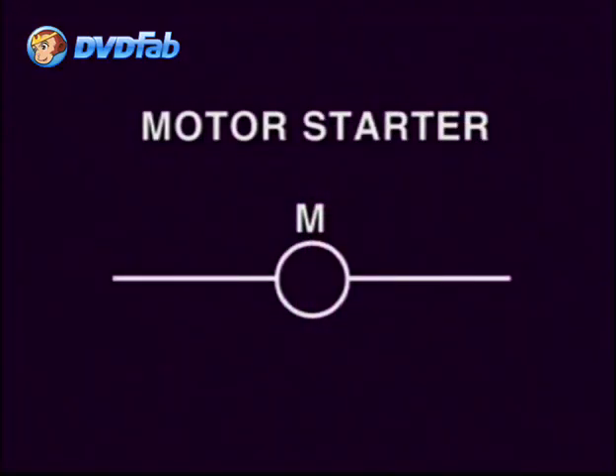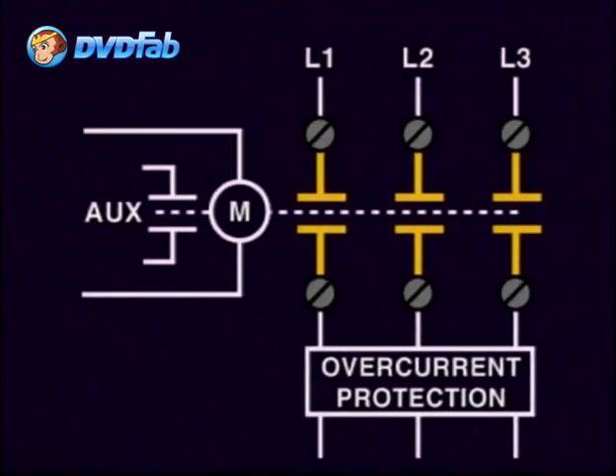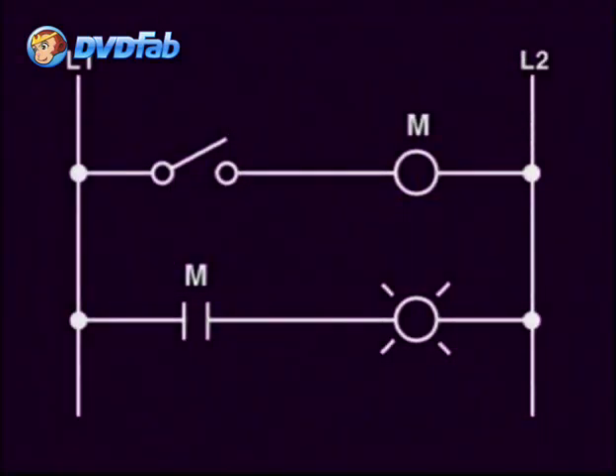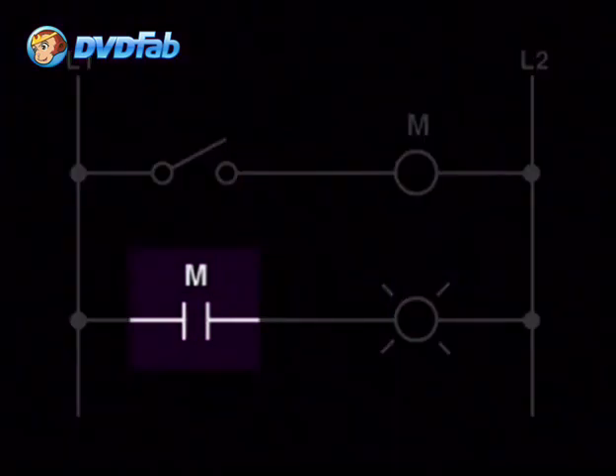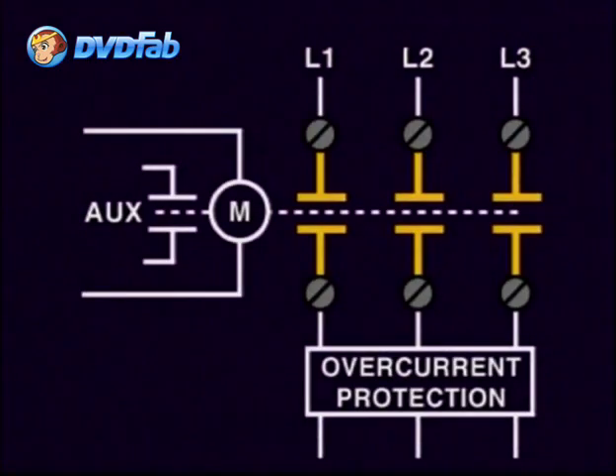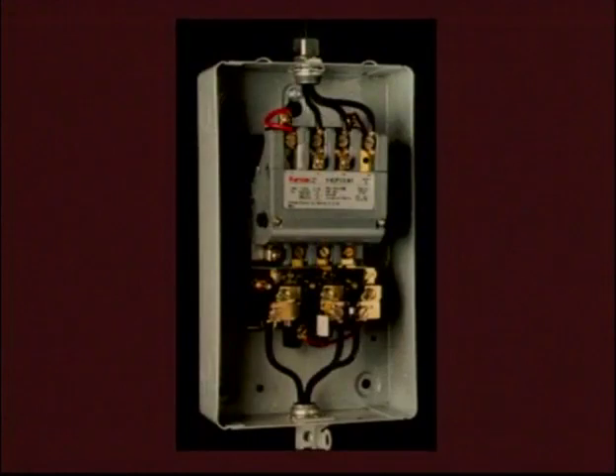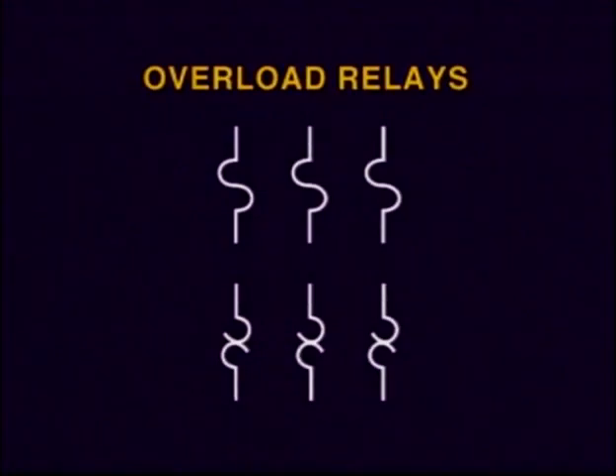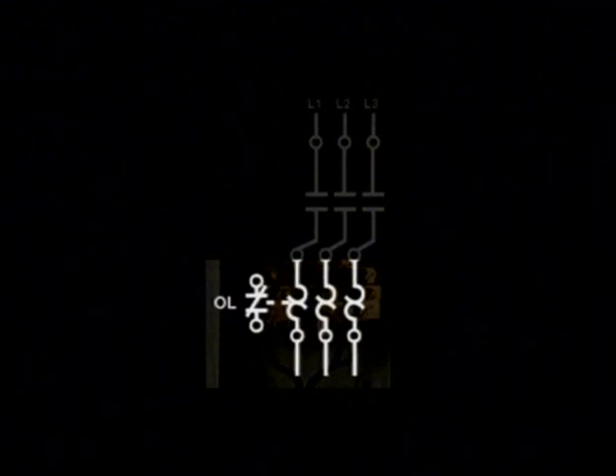Motor starters are represented by this symbol in a ladder diagram, while its power contacts are represented like this. Motor starters also have auxiliary contacts which are used for interlocking connections with start-stop circuits and other components in a ladder diagram. The power contacts are generally represented in a wiring diagram where they connect to the motor being controlled. As we mentioned earlier, starters provide protection to the motor with overload relays, which are represented by either of these symbols. These overloads are encountered below the contactor section of the starter. The overload relay controls a normally closed contact, which is called the motor overload contact.